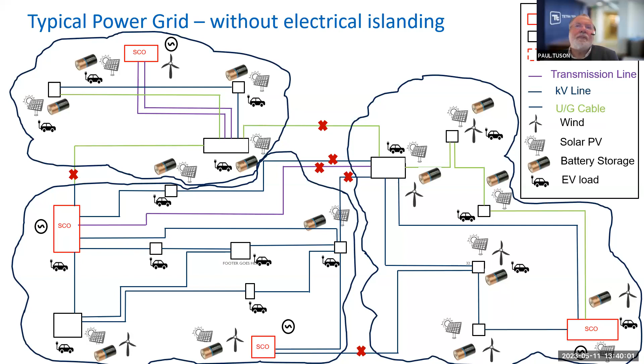As Barbados is in the Caribbean and in the hurricane belt, it is prone to severe storms and infrastructure damage. One way of improving system resilience is to divide the island into electrical sub-islands, as shown in the figure. If a storm damages assets on the right-hand side, those bold red circuit breakers can be opened, and the two left-hand islands can operate while the right-hand island is restored, then resynchronized using resynchronization relays between the islands. The load and generation in the divided islands should be matched so the islands can operate effectively.